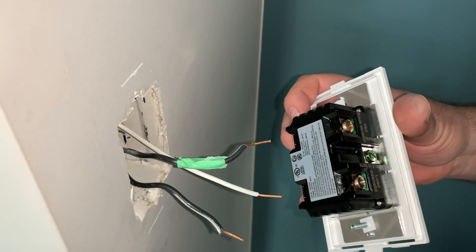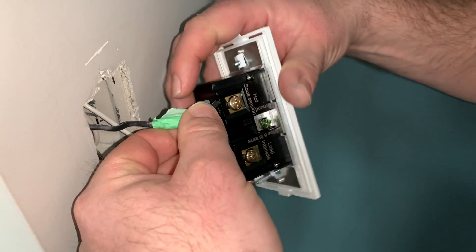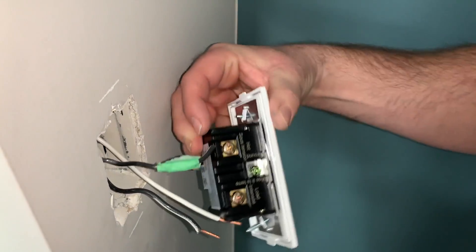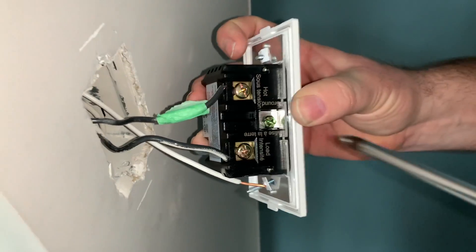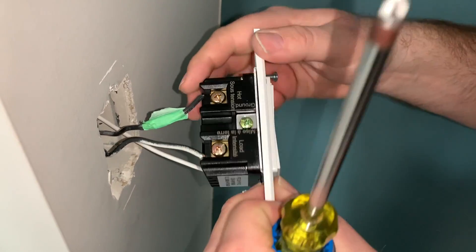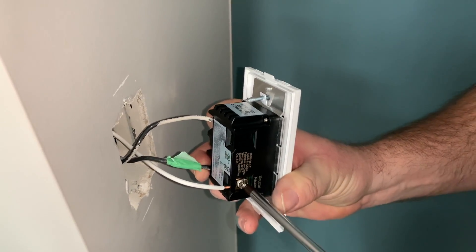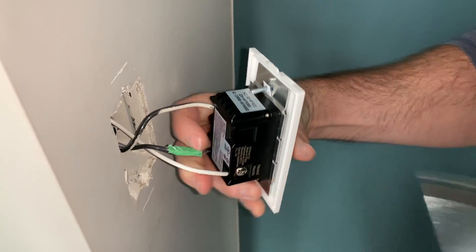Now we're going to make our connections. We put the hot wire into the hot terminal and make sure it's good and tight. Next, grab the load wire that goes to the fixture and fasten that down. Finally, flip the switch over and install the newly added ground wire — make sure the conductor stays all the way in as you're tightening down the fasteners.